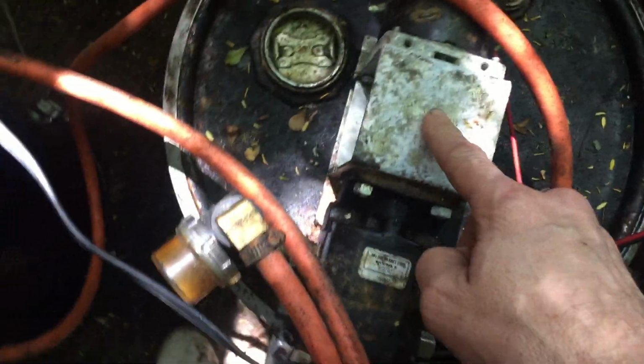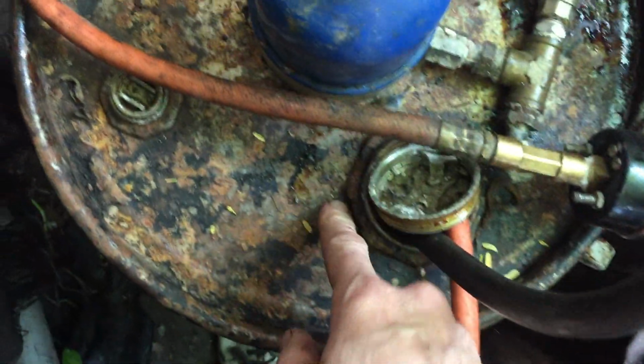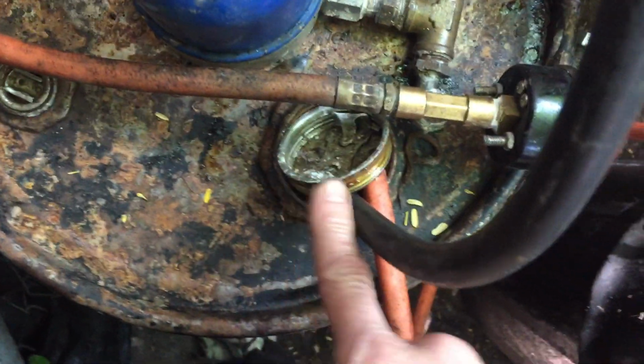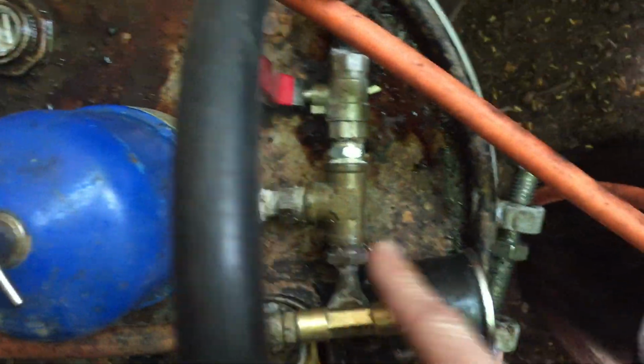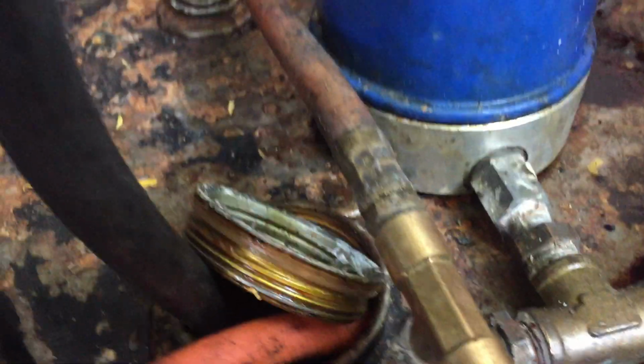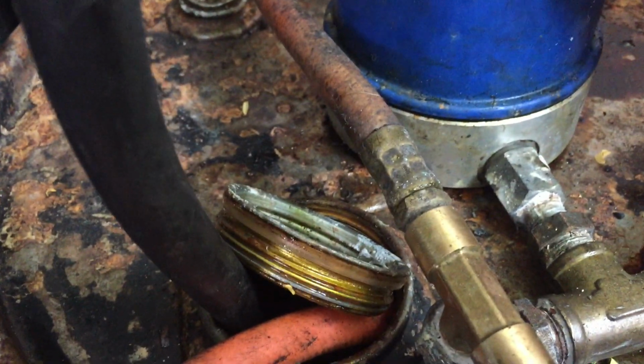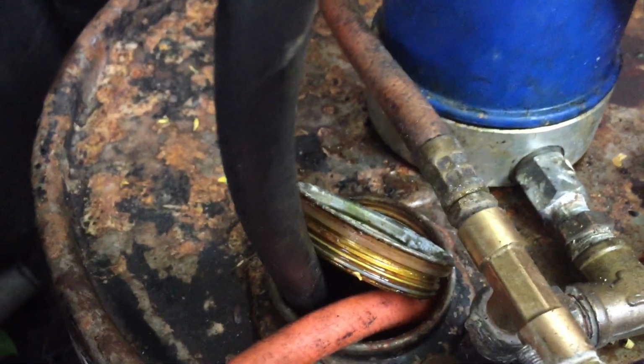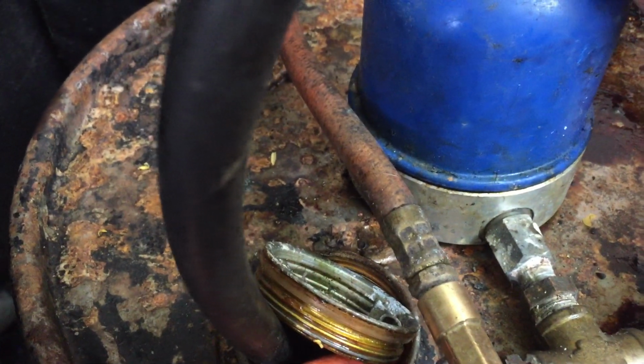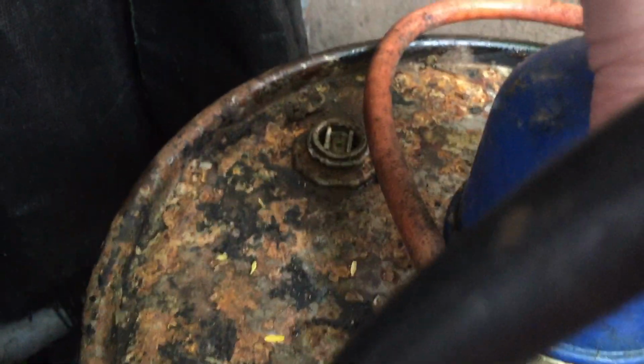The pump is taking oil from inside this metal container. It goes through these fittings, and up to this little gauge that shows the pressure. The pressure is adjusted by this bypass valve. When you open it, the fuel flows very quickly, and when you close it, it starts to restrict because it has to go through the centrifuge.